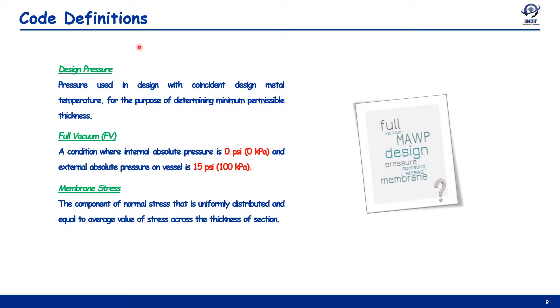One of the most important code definitions is design pressure — the pressure used in design with coincident design metal temperature. Design pressure is used to determine the required thickness of a component. In most cases it comes from the client or user and represents the most abnormal operating condition. If no design value is provided, take the maximum operating condition and add 10% to obtain the design pressure. In some cases, design pressure can be taken as equivalent to MAWP, the maximum allowable working pressure.